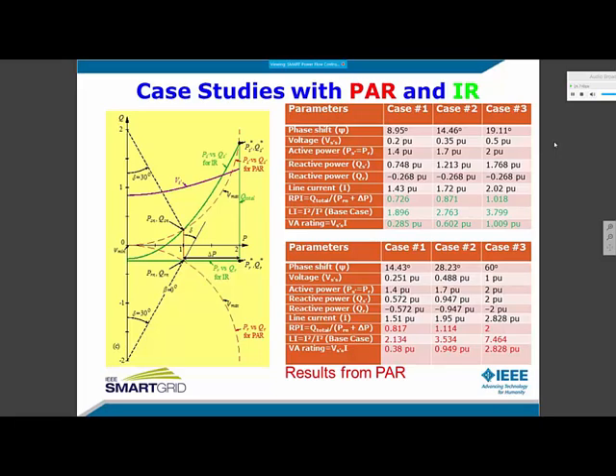For the same three operating cases of P flow enhancement, it shows that the load is burdened with the responsibility of supplying a higher than necessary amount of Q flow when a phase angle regulator is used compared to when an impedance regulator is used. The loss in the line is also increasing, and the rating of the solution is also increasing. For example, in this table, it shows that for a 100% increase in delta P, a 100% increase in the power flow in the line, the reactive power index is 2 versus 1 in an impedance regulator. The loss index is 7.4 versus 3.7 in an impedance regulator, and the rating is 2.8 in a phase angle regulator versus 1 in the impedance regulator. And the lower the number, the lower the cost.